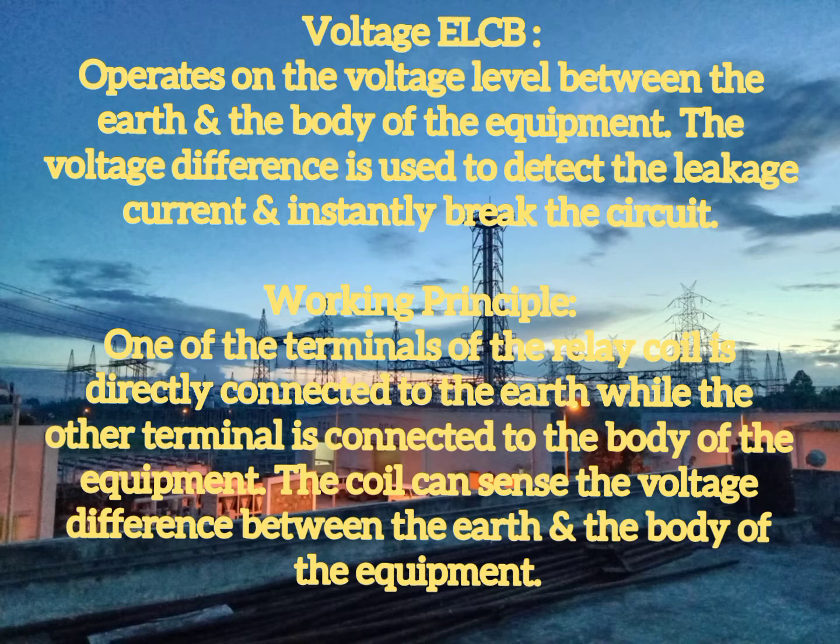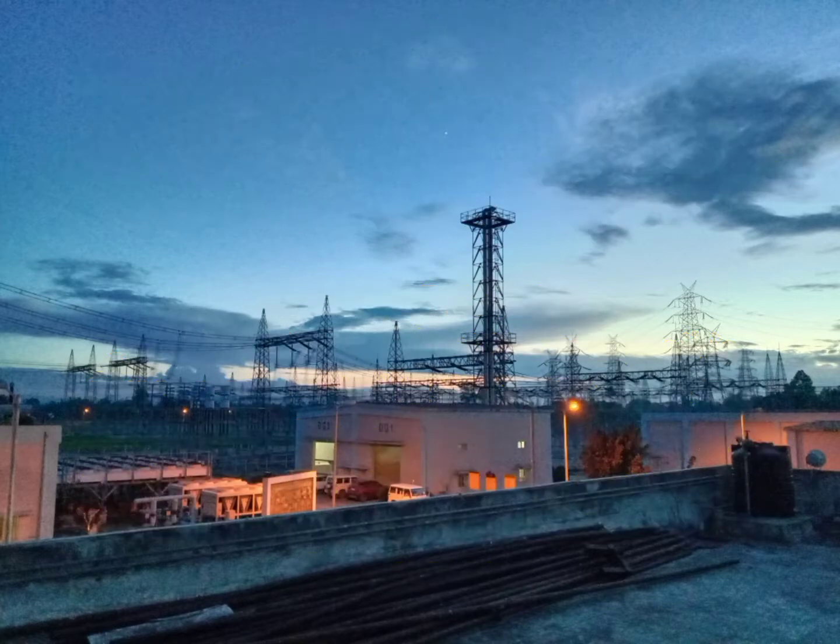Then, the working principle of voltage ELCBs. One terminal of the relay coil is directly connected to the earth, while the other terminal is connected to the body of your equipment. So the coil can sense the voltage difference between the earth and the body of the equipment, and then triggers the relay coil, and automatically your voltage ELCB gets activated.